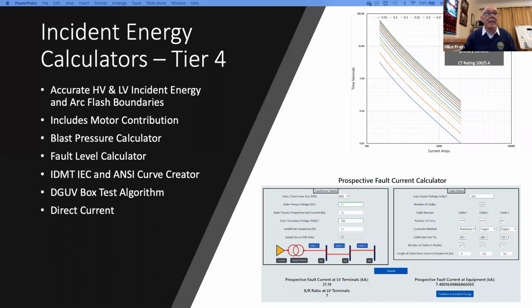So finally, as the tier 4 circuits, I think I've described the prospective fault current calculator, which is exactly that. It allows you to get an accurate high voltage and low voltage incident energy level and arc flash boundaries, and does include motor contribution, as I've suggested. There are other calculators there, and not all listed, but there's blast pressure, fault level, which is shown on, sorry, that's shown on the bottom there, the prospective fault current calculator at that point. My PC was sort of hiding it off the screen there.